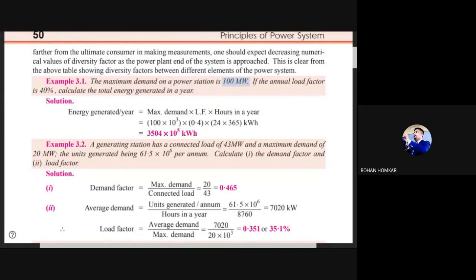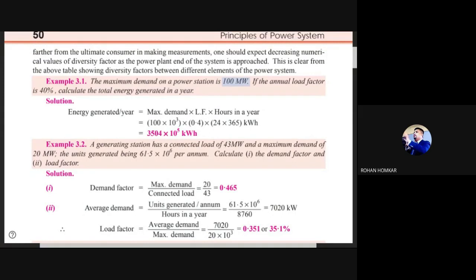Example 1: Maximum demand on the power station is 100 MW and the annual load factor is 40%. Calculate total energy generated in a year. Total hours in a year = 365 × 24 = 8760 hours. Convert 100 MW to kilowatts: 100 × 10³ kW. Load factor 40% = 0.4. Using: average load = maximum demand × load factor.